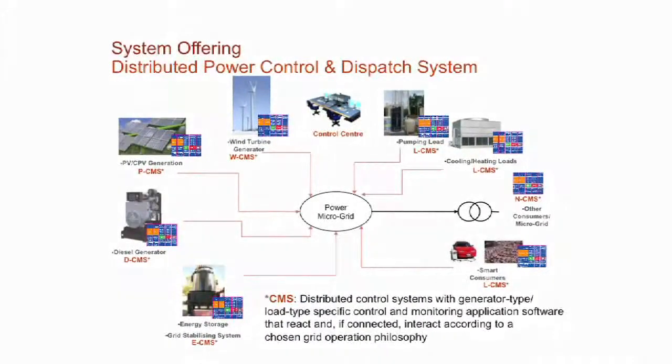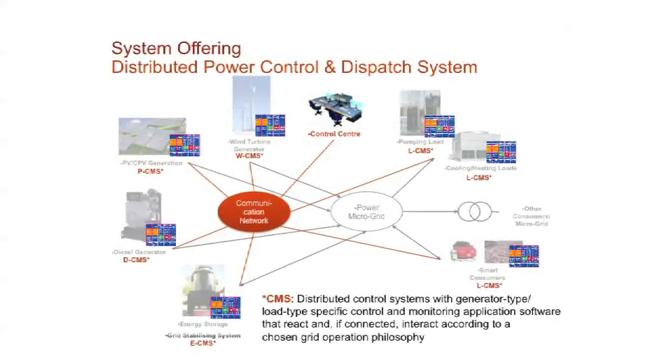Okay, we've got a power grid, a micro power grid that we're going to be looking at in terms of the fluctuating of the power. Obviously looking at the flywheel down here, as we've said, generation, different sorts of generation, and also on the load side. We also have a communication link to solve this problem. So we've got the little computers. It's a distributed control system. So we've got two sides to this. We've got the power grid control, which is the stabilising, and we've got the communication network to do energy flow management. There's two sides to the story, and the control and the communication network. No central computer, it's distributed control. This is all established, it's out in the field working. I'll show you some examples in a minute.